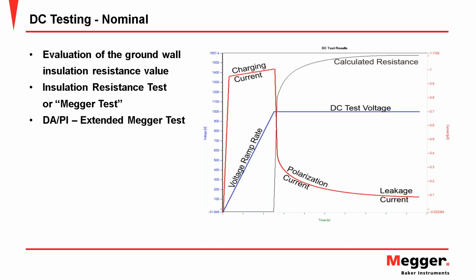If we extend that, a MEGGER test is typically 1 minute from the point of reaching test voltage. And we see here in the graph, what happens is we have this charging phase where we increase voltage to our test voltage, hold for, again, say a minute, and we allow the circuit to charge. Initially, we have this initial charging current, which is really defined by the circuit characteristics of capacitance, inductance, resistance, and the rate of change at which we get to test voltage. Once test voltage is achieved, we hold that value for 1 minute, and we allow that current to decay asymptotically over time as the circuit charges, and then the insulation literally polarizes so that the molecules in the insulation are basically aligning with the electric field that we're applying during the test.